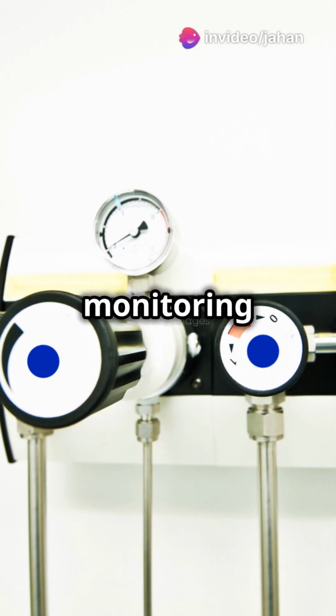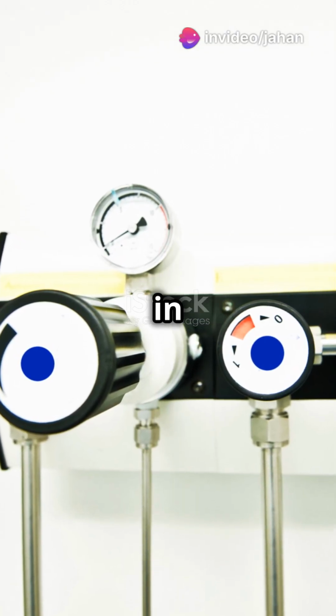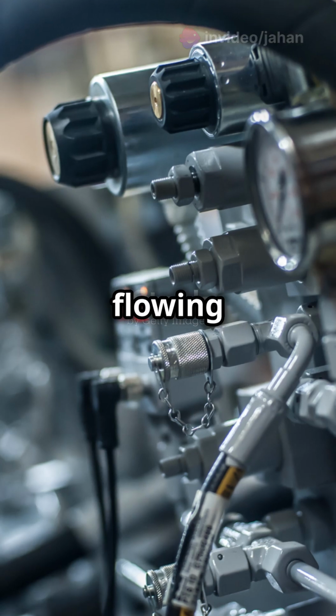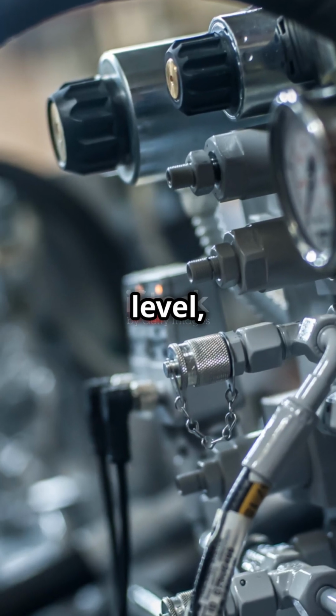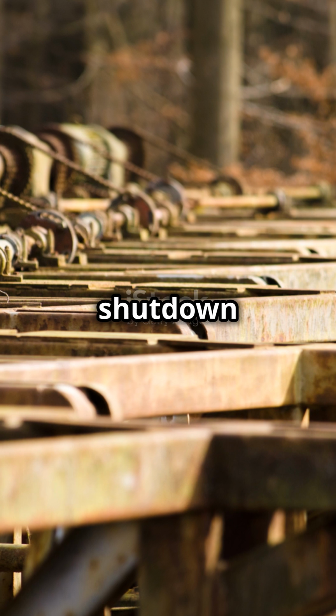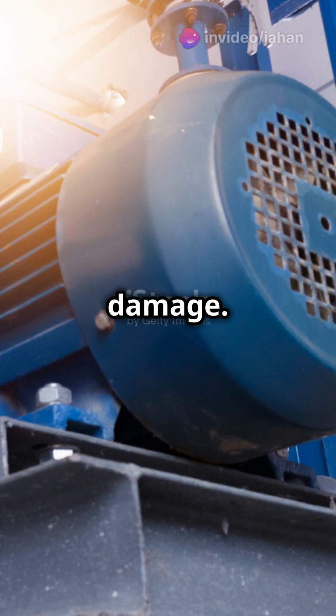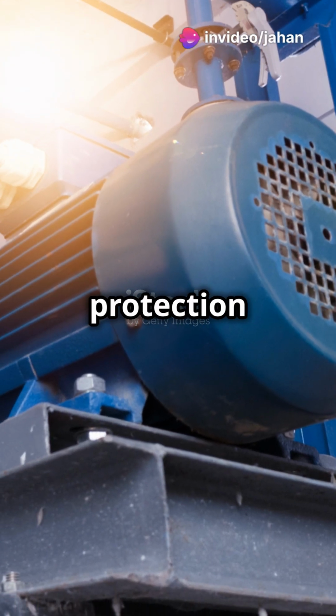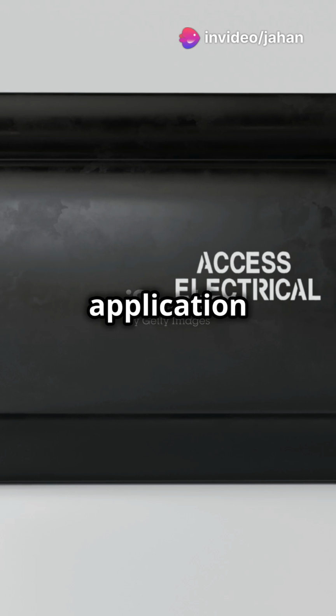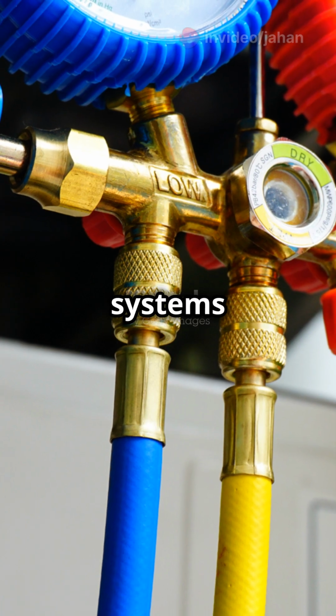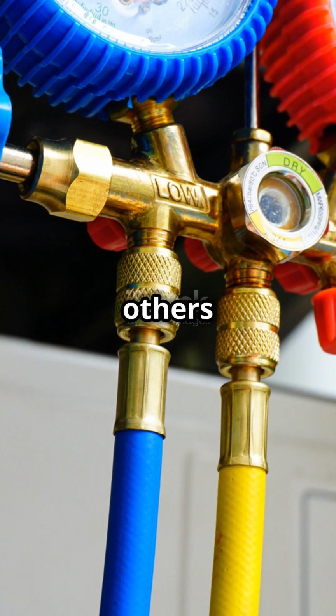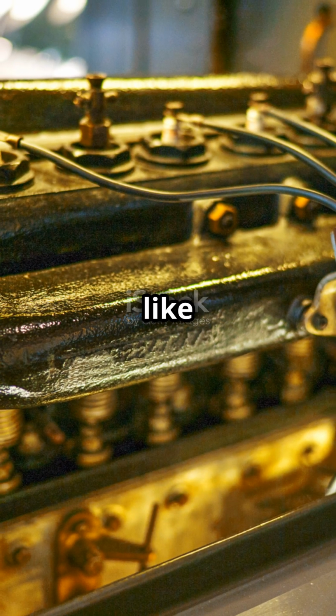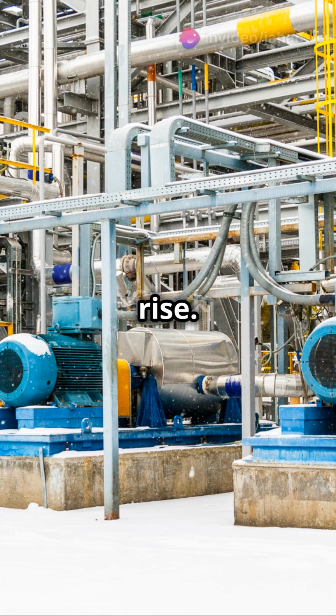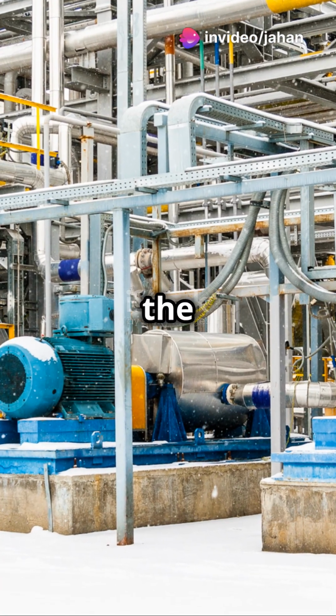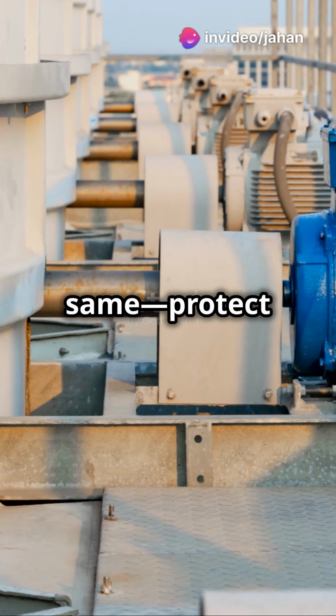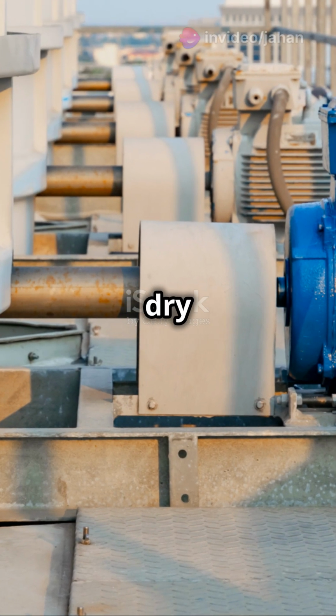Another method involves monitoring pressure or flow sensors in pump systems. If no fluid is flowing, or if pressure drops to an unsafe level, the system can activate a shutdown process to prevent motor damage. There are different ways dry run protection can be implemented, depending on the application and the type of motor. Some systems use direct monitoring, while others rely on indirect measurements like vibration or temperature rise. Regardless of the method, the core goal is the same: protect the motor from damage due to dry running.